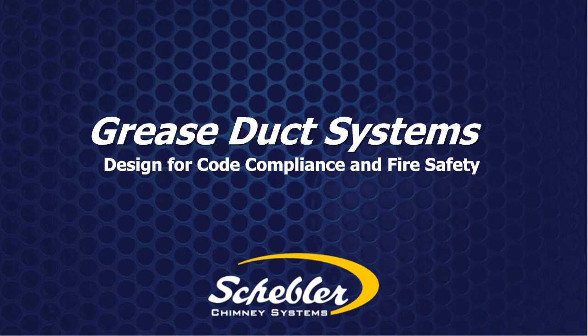Okay, if an old duct system had zero clearance by design, does it need to have a fire wrap? No, it doesn't. Since the product is pre-insulated, it is zero clearance as it leaves the factory. So we've got an inner liner, in that case, that project had 4 inches of insulation, and an outer shell. That is already considered zero clearance to combustibles and fire rated. So there's no on-site insulation that would be added, only just to cover those gaps in the assembled joints, which is supplied by the manufacturer.